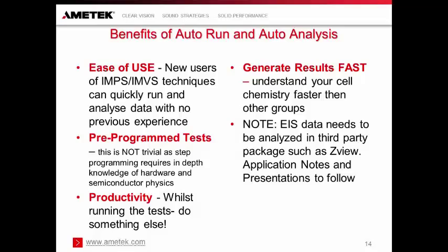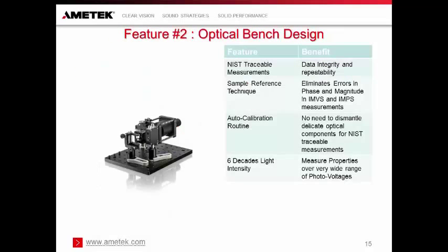So in the second part of my presentation, I want to focus on some of the features of the optical bench design. Clearly this is an optical measurement system, and therefore due care and attention must be given towards the optics and correct implementation of the optics. And so the features I'll be discussing include NIST traceable measurements, a sample reference technique for IMVS and IMPS, an auto-calibration routine, and finally 6 decades of light intensity. Well, that's a change in the order of 1 million times in light intensity available with this bench, offering us a wide range of measurement properties.